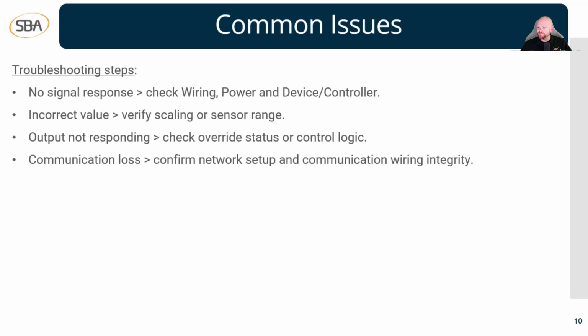Next up, we're going to talk about some really common issues that you guys might see when doing these, with troubleshooting steps. So for the first one, say we have no signal response from a temperature sensor. To check this one, when we're talking about troubleshooting, we would do a wiring check. We verify that the wire's not cut somewhere, or maybe we have a wire that didn't get terminated correctly and maybe it popped back out of the terminal screw.